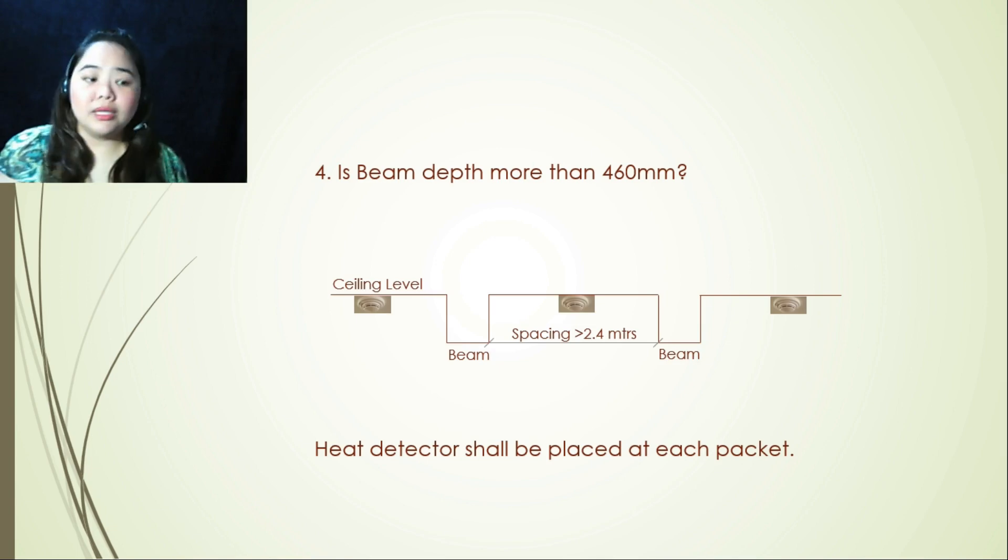On to our last argument: beam depth more than 460 millimeters. And also, if the spacing is more than 2.4 meters, because of the spacing and the distance, you should now put the heat detector in each pocket. So let's take a look at the illustration here. On to your ceiling underside, and then here another one, then you can also place it here. So again, heat detector shall be placed at each pocket.